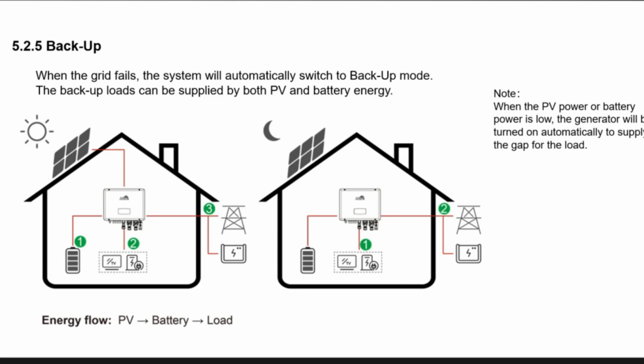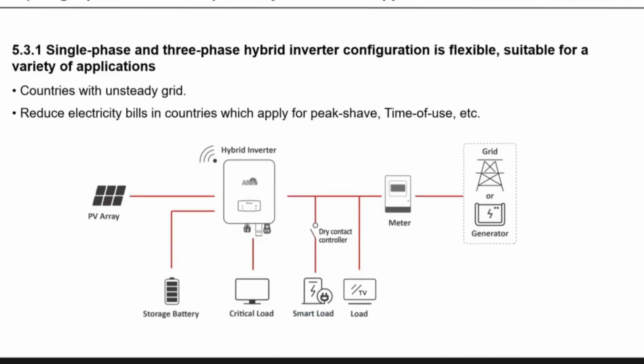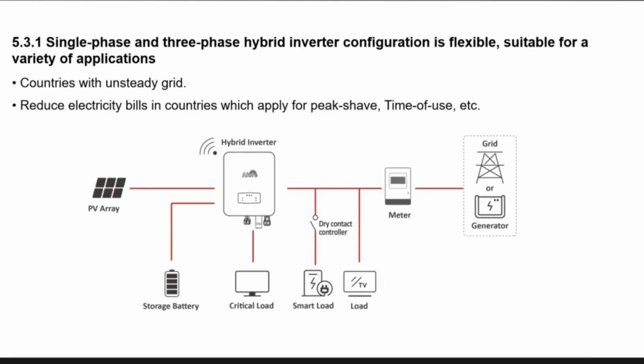So the last one is backup mode. When the grid fails, the system will switch directly to backup mode, off-grid mode. So the energy flow will be PV providing energy to the battery and to the load. When the PV power or the battery power is low, the generator will be turned on automatically to supply the gap of the load. Under these conditions, if the system adds a generator as a backup, especially during the nighttime or dawn in the morning, the generator will make up the gap for the load. This part is the same way Dan explained before.